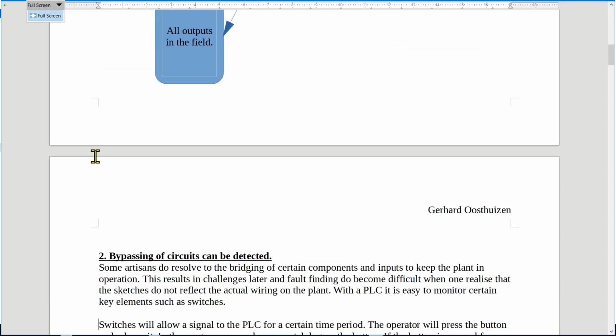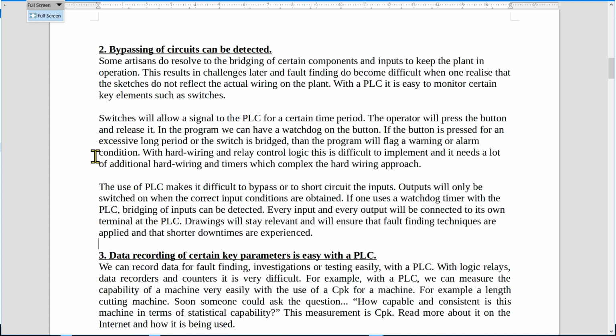Now the next one that is important, why PLCs? Bypassing of circuits can be detected. Some artisans do resort to the bridging of certain components and inputs to keep the plant in operation. Now, this results in challenges later, and fault finding becomes difficult when one realizes that the sketches or the drawings of the machine do not reflect the actual wiring on the plant.